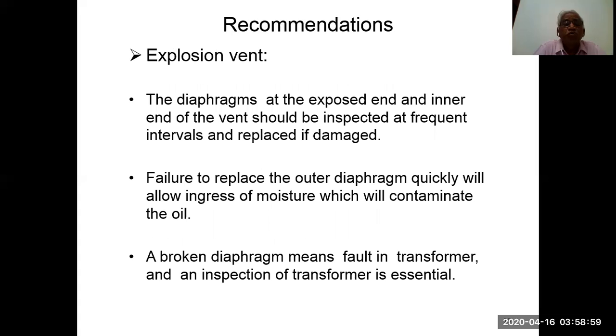Recommendations: explosion vent. The diaphragms at the exposed end and inner end of the vent should be inspected at frequent intervals and replaced if damaged. Failure to replace the outer diaphragm quickly will allow ingress of moisture, which will contaminate the oil. A broken diaphragm means a fault in the transformer, and an inspection of the transformer is essential.